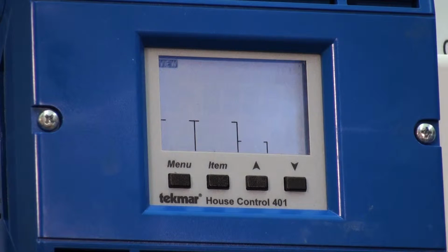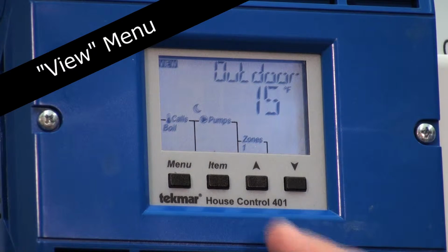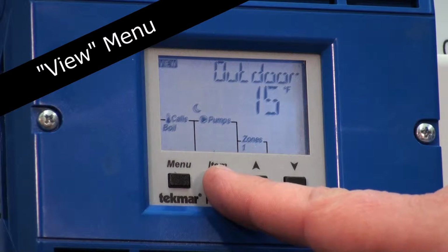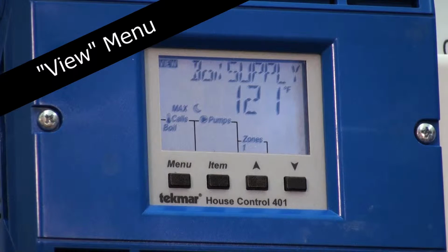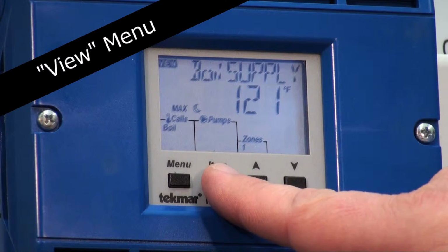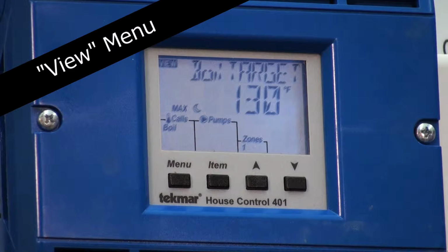Pressing menu again takes us back to the top, and under view, now you want to press the item button. Right now we're showing the outdoor temperature is 15 degrees outside. Press the item button. Now you're going to see your boiler supply water temperature, what is currently being sent out of the boiler for your water temperature. If you press item again, you're now looking at the boiler target temperature. This is what the boiler is targeting for delivered water temperature to your house based on outdoor temperature and indoor temperature feedback from our thermostats.